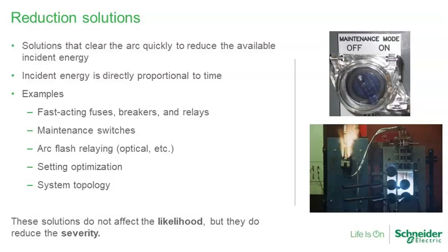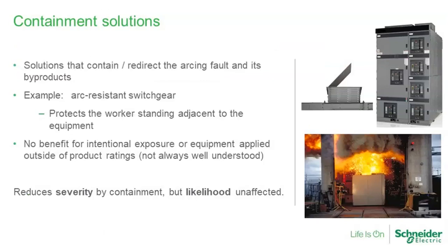If we put a maintenance switch in a piece of equipment, we may not reduce the likelihood. We may not make it more or less likely to actually create an arc flash if we're going to go in there and do some voltage testing, for example. But the goal of these generally would be to reduce the severity. If an arc does happen, let's clear it more quickly and reduce the level of energy that the worker is going to be exposed to. The next category of solutions treats things a little bit differently. The next one is containment.